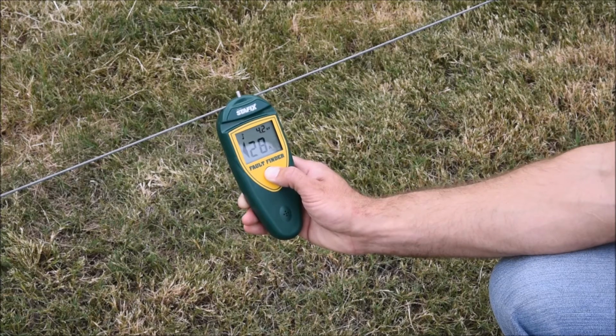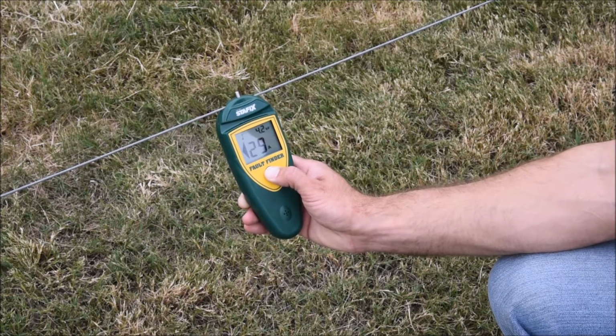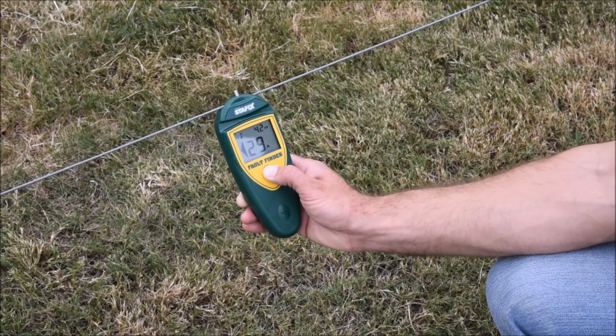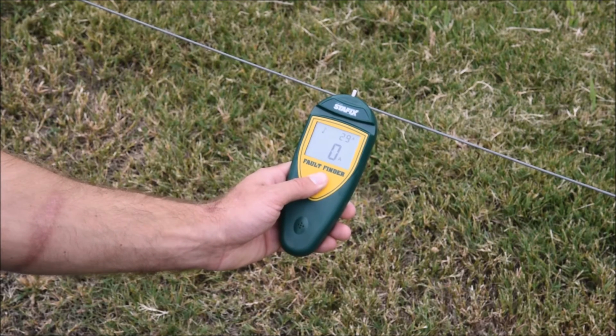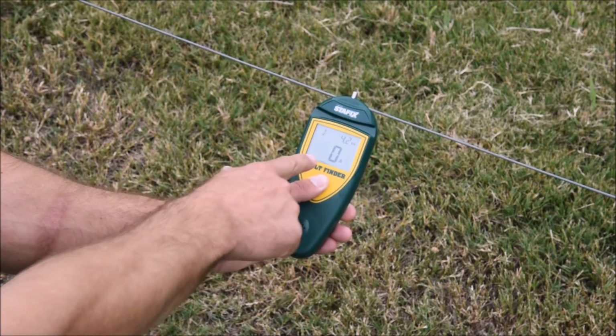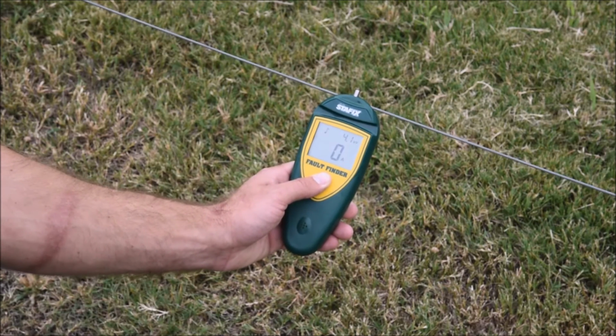You can take voltage readings every 200 yards to determine the kilovolts and the amperage. Once we get beyond the problem, the amperage reading will drop. So once we're beyond the fault, our amperage reading goes down to 0, yet our voltage reading stays the same.